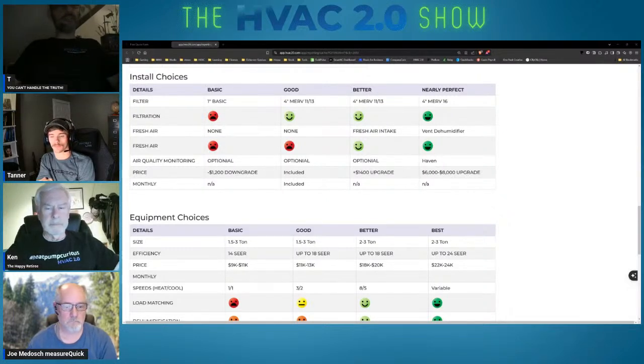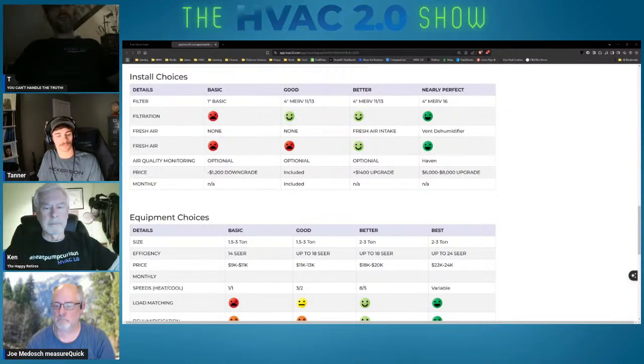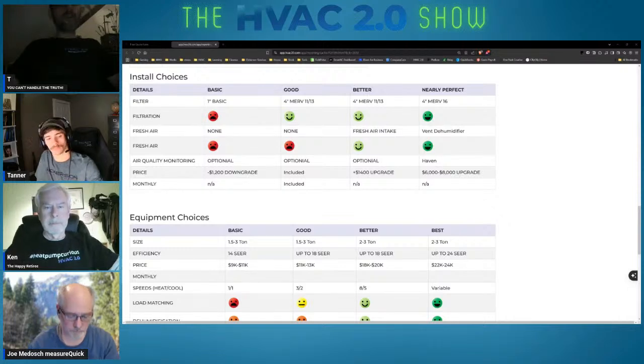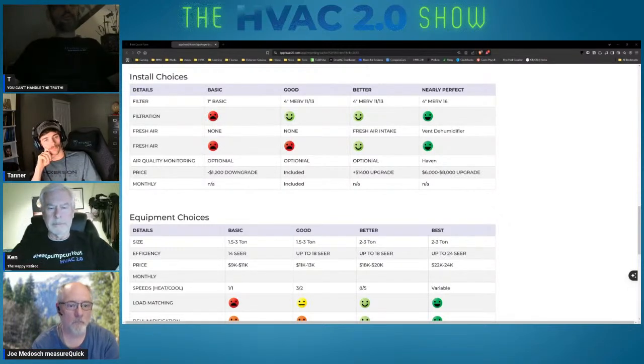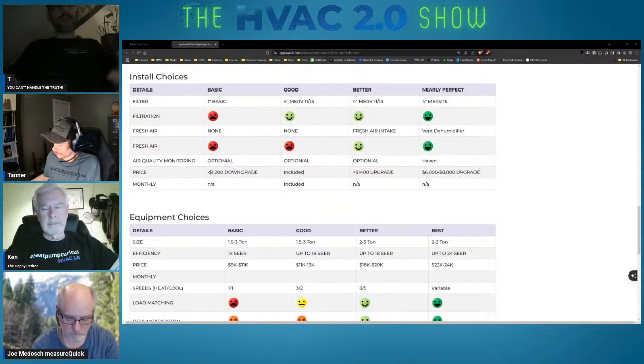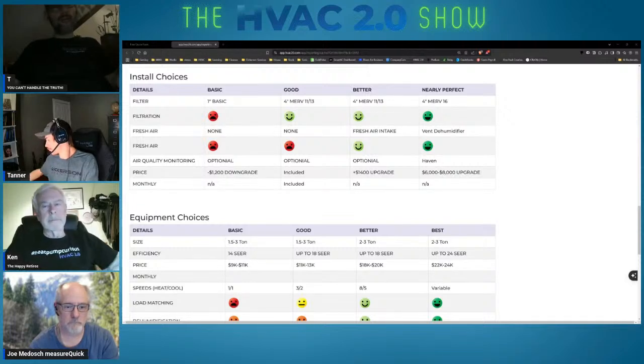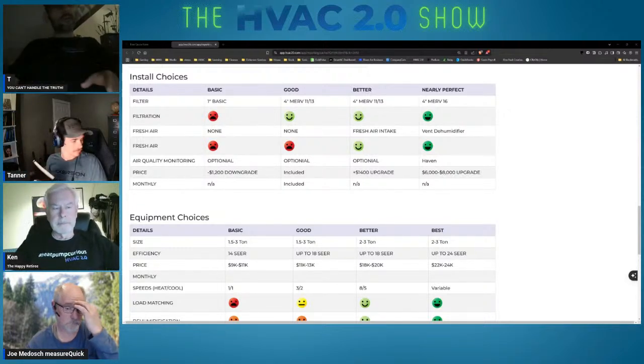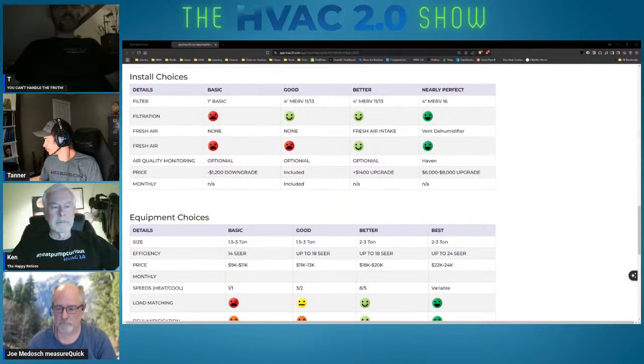New equipment doesn't like being attached to insufficient ductwork. So if your duct constraint is 2.5 tons, it's a really bad idea to put something bigger than 2.5 tons with this new equipment. Older equipment, less efficient but more robust, could handle a 4-ton unit on 2.5 tons of duct and get away with it. Granted, you got 12 years out of your old equipment — you probably would have gotten 20 if it had been properly sized to the ductwork, or the ductwork properly sized to the equipment. One thing we've found is if you oversize the equipment to the house, you'll have trouble getting your 6 functions. So all of this becomes little narratives helping the homeowner understand, tying the 6 functions into the specification they're building.